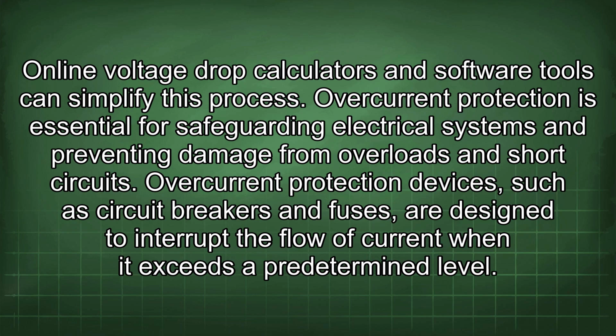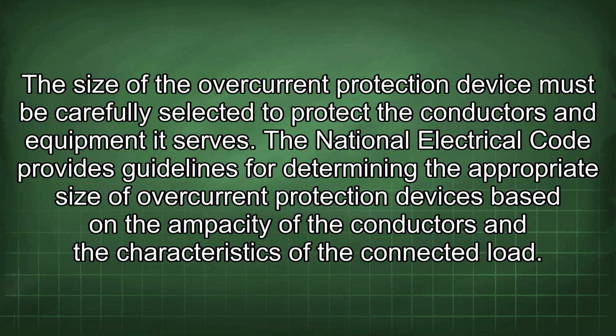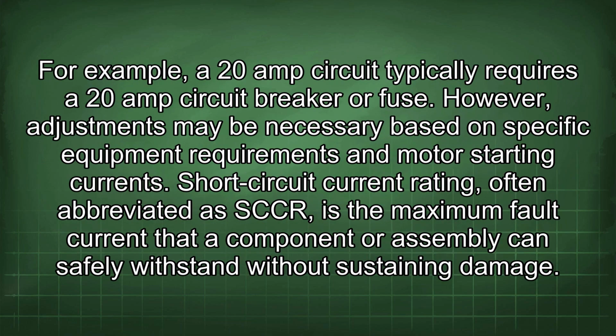Overcurrent protection is essential for safeguarding electrical systems and preventing damage from overloads and short circuits. Overcurrent protection devices, such as circuit breakers and fuses, are designed to interrupt the flow of current when it exceeds a predetermined level. The size of the overcurrent protection device must be carefully selected to protect the conductors and equipment it serves. The National Electrical Code provides guidelines for determining the appropriate size of overcurrent protection devices based on the ampacity of the conductors and the characteristics of the connected load. For example, a 20 amp circuit typically requires a 20 amp circuit breaker or fuse. However, adjustments may be necessary based on specific equipment requirements and motor starting currents.